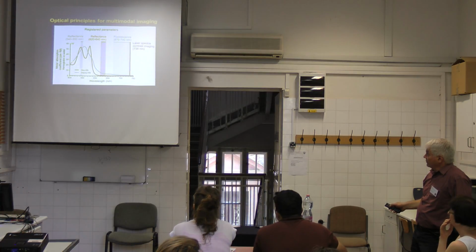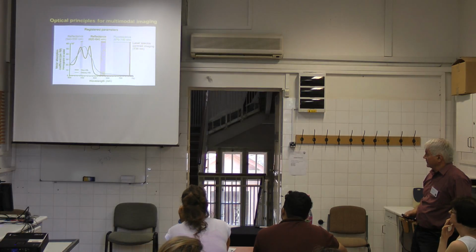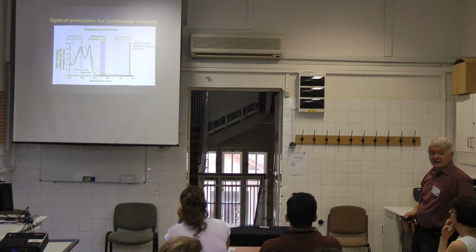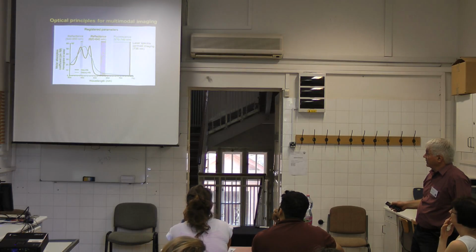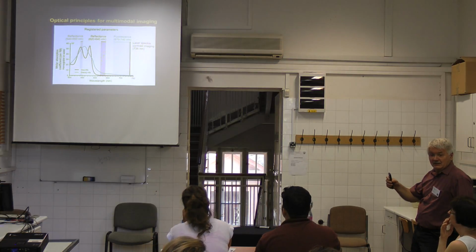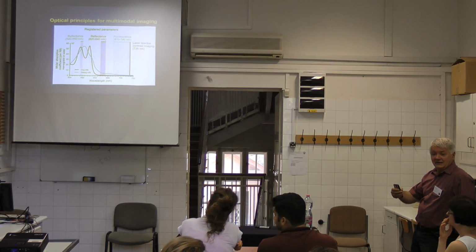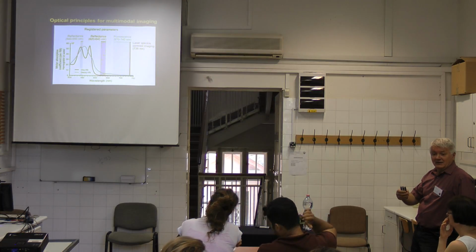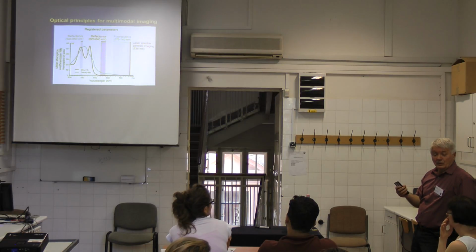And there is another form where there is no oxygen, and it is absorbing in this way. What can we use? If you use this wavelength where both the oxygenated and the deoxygenated are absorbing at the same intensity, we can make a measurement which is independent of the hemoglobin oxygen concentration. Therefore, it reflects the local blood volume.